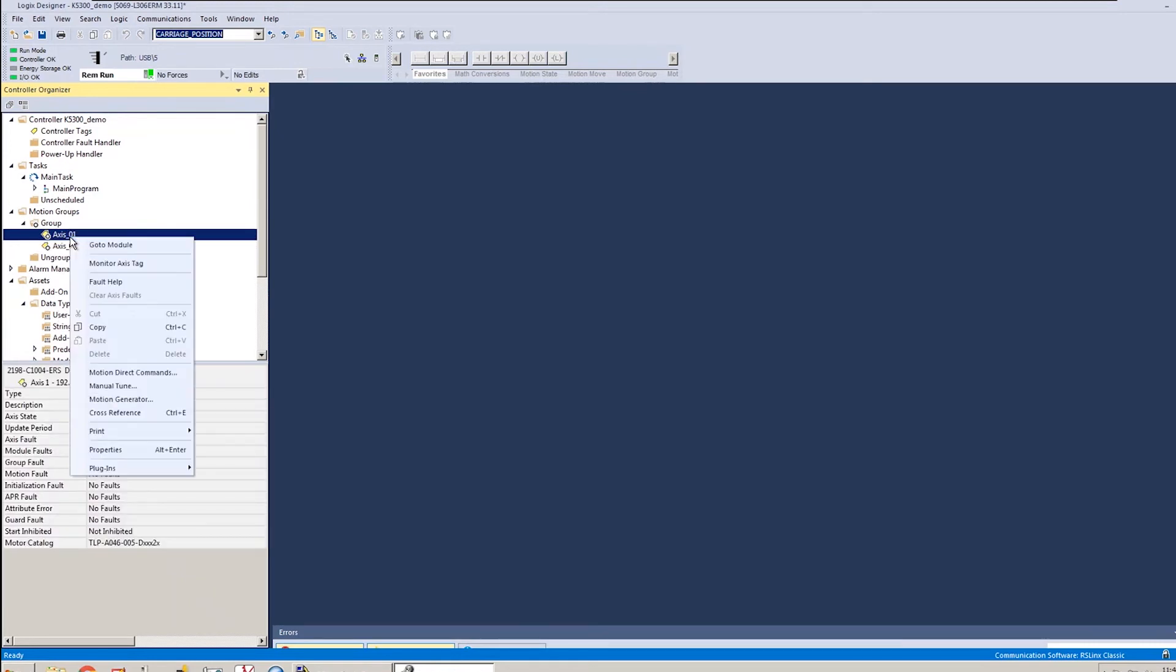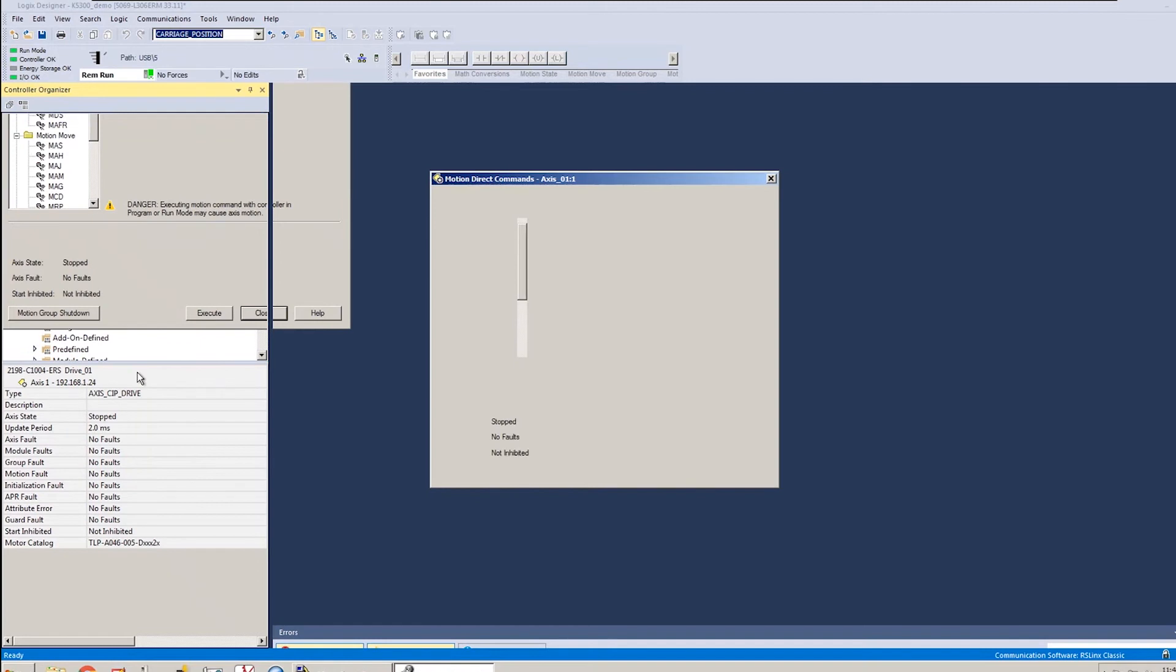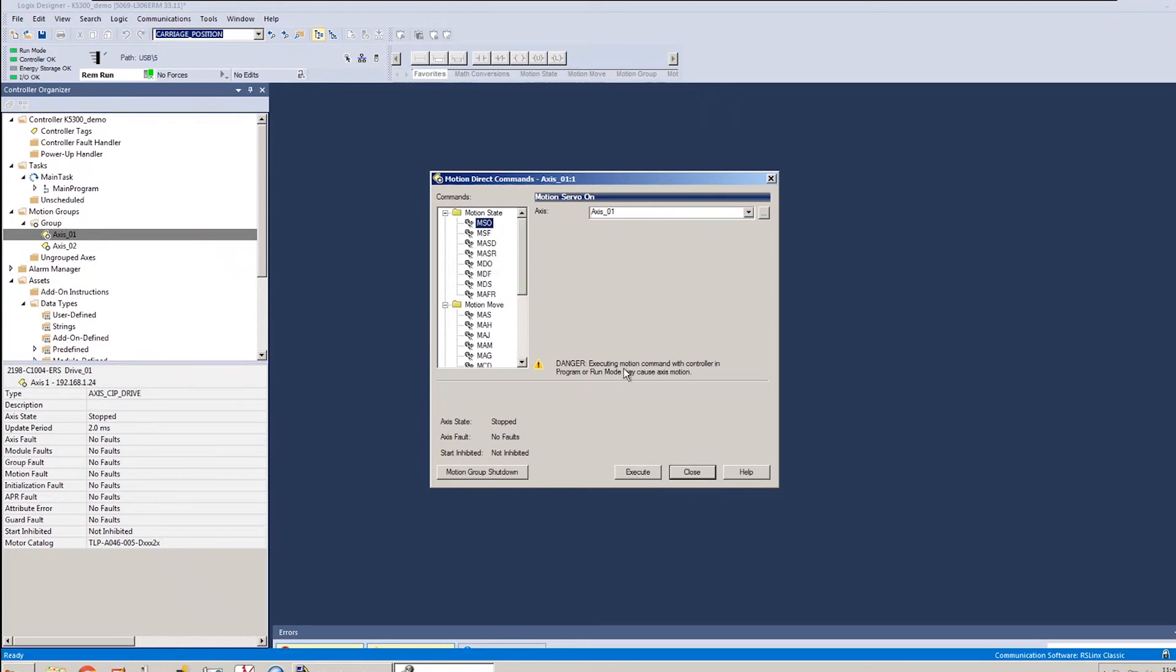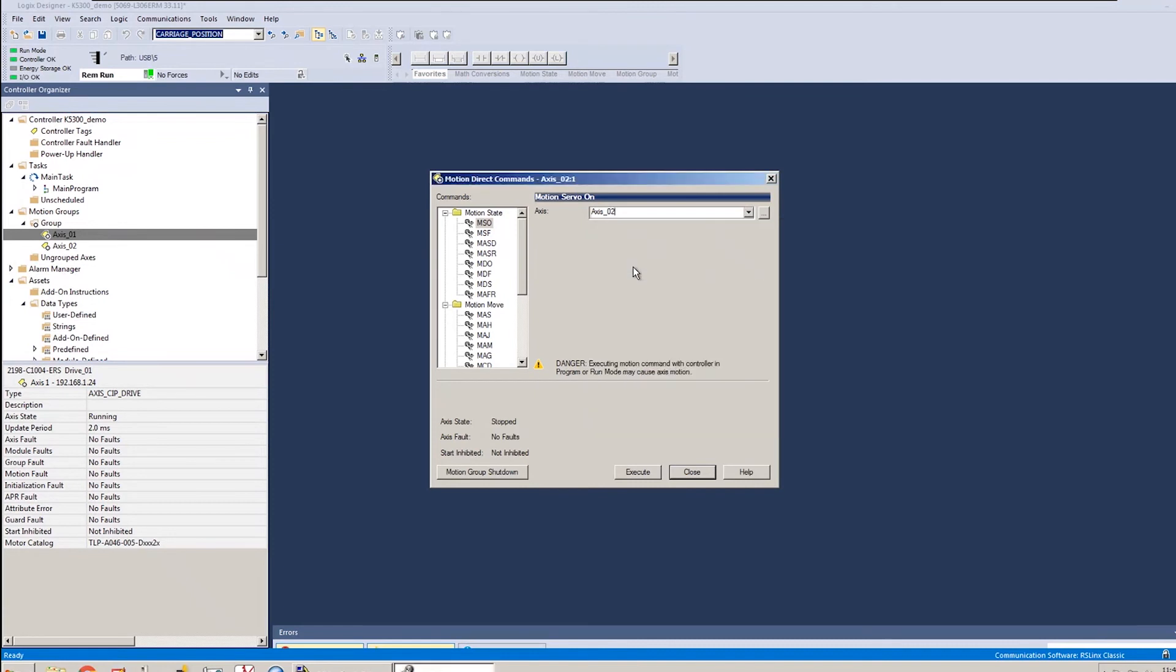I'm going to right click axis one and select motion direct commands, which will launch the motion direct command window. The first instruction I'm going to run would be the motion servo on MSO. Just select it. Keep axis one going there and I'm going to hit execute. You'll see when I do that, that the axis state goes from stopped to the running state. The next thing that I'm going to do is I'm going to just switch over to axis two and enable axis two as well.